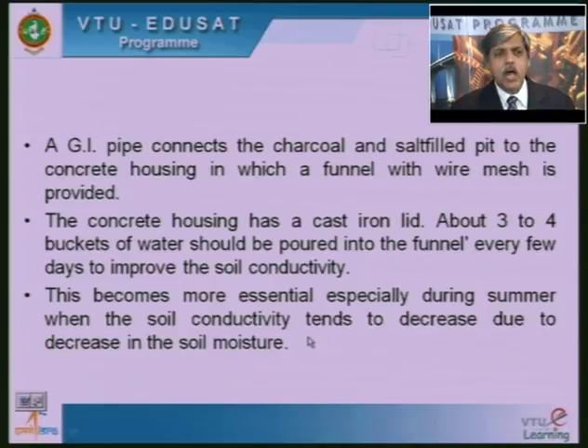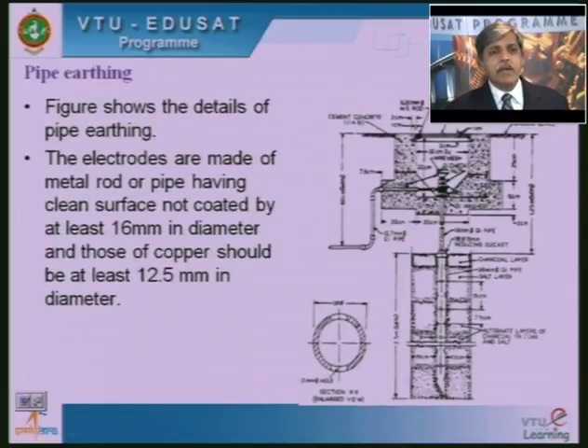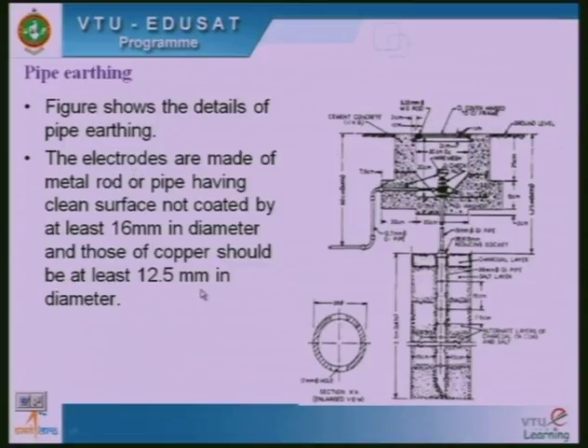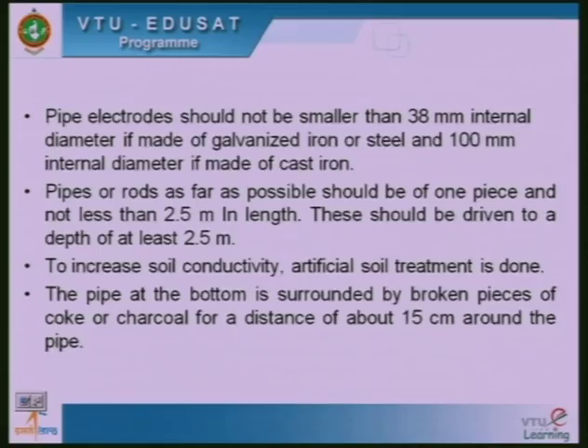So, like this I have a pipe earthing. The method of earthing is almost the same, only thing is I will not be using a metal plate here, I will be using a metal pipe, GI pipe or a copper pipe. Okay. 12.5 mm in diameter or at least 16 mm diameter. Okay. So, I will be using a pipe, therefore I call it pipe earthing. The method of earthing is everything same. So, you can just go through this.